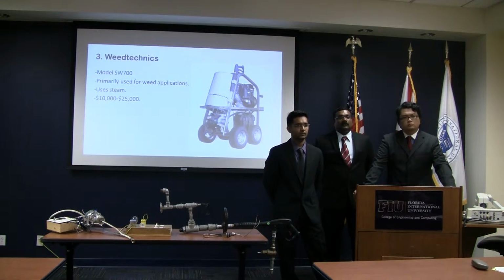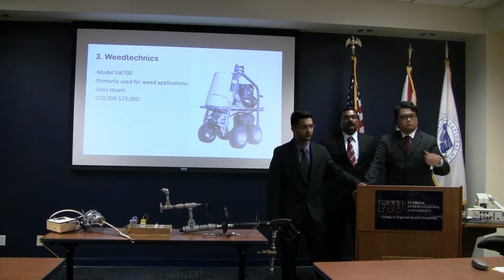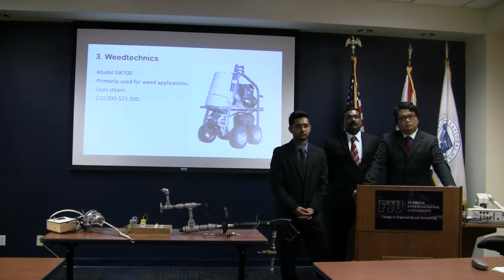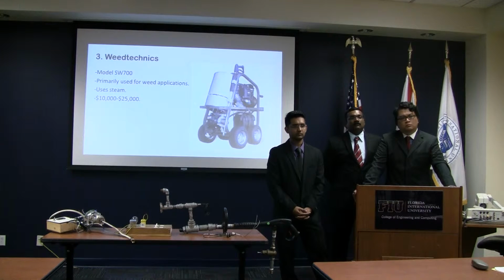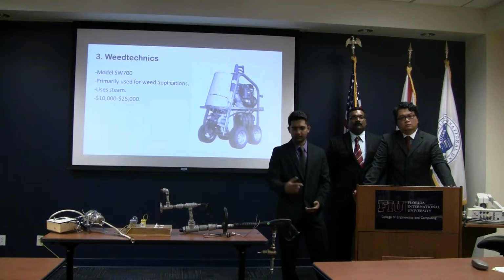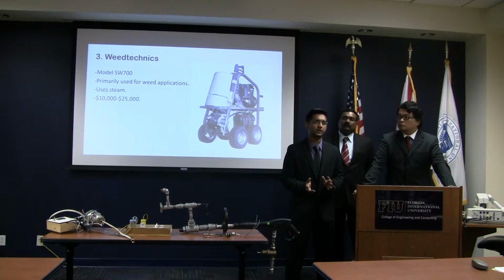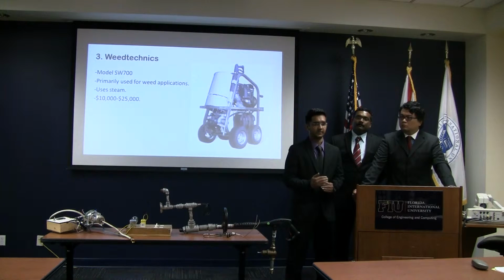No, we're saying the same thing. Why? So you're doing a design, correct? You're doing a design to try to reach 95. That was your goal. You felt in your design, you did some initial calculations that a 2000 watt heater would be enough, right? Why was that an incorrect calculation, and what can you do to improve that calculation to show that 2500 is enough? Well, we introduced a 500 watt heater basically on a trial and error basis to see if that would be enough.